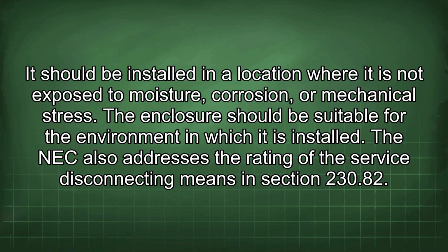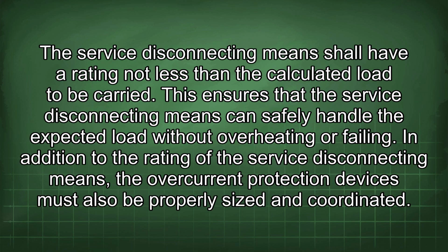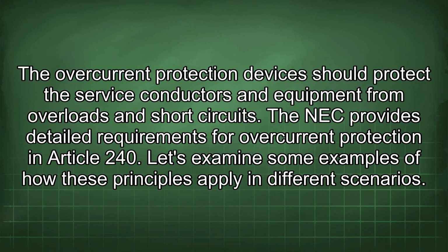The NEC also addresses the rating of the service disconnecting means in section 230.82. The service disconnecting means shall have a rating not less than the calculated load to be carried. This ensures that the service disconnecting means can safely handle the expected load without overheating or failing. In addition to the rating of the service disconnecting means, the overcurrent protection devices must also be properly sized and coordinated. The overcurrent protection devices should protect the service conductors and equipment from overloads and short circuits. The NEC provides detailed requirements for overcurrent protection in Article 240.